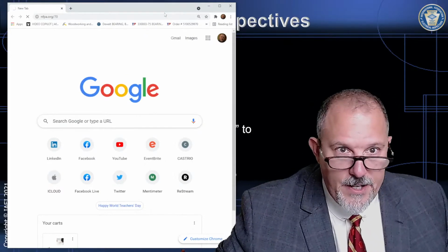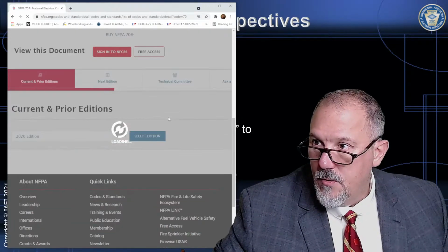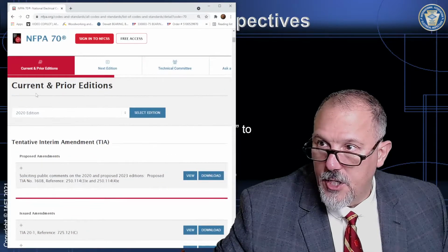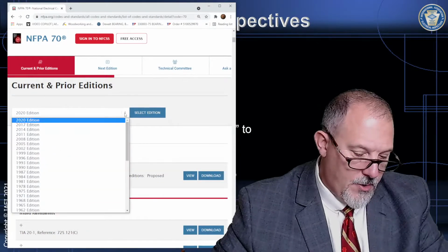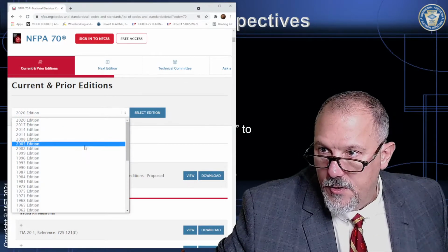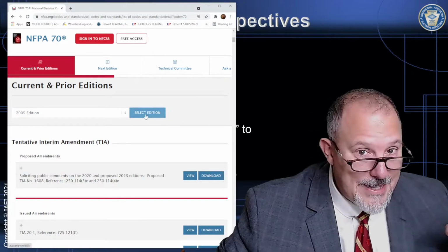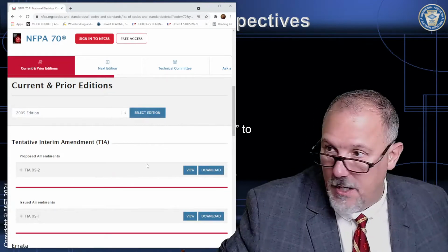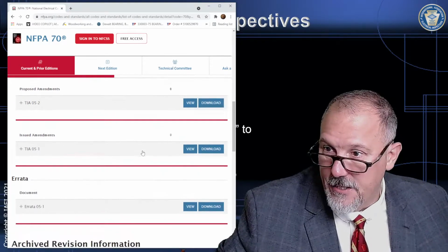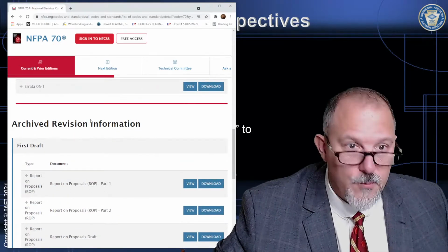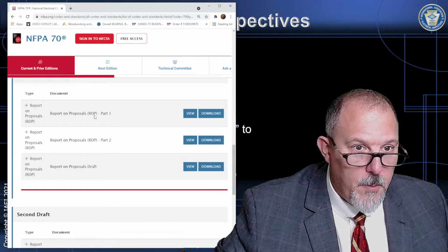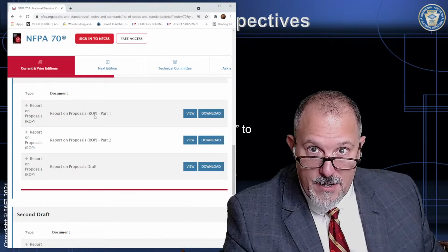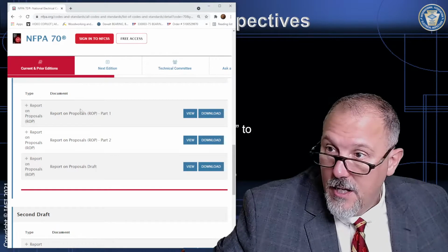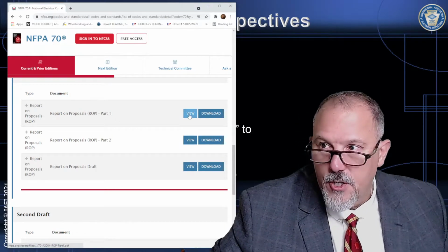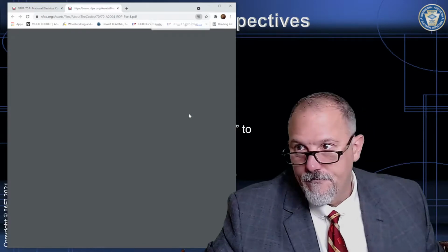Go to NFPA 70. Scroll down and go to current and prior editions. And we're on the 2005 version. So you select your 2005 version and hit select edition. That will change everything down below. Don't forget to hit select edition. Scroll down to where you see archived revision information, and you'll see report on proposals. Now this one had a part 1 and part 2. That means there are a lot of public inputs or a lot of proposals made. Because this is in 110, good chance of it being in part 1.